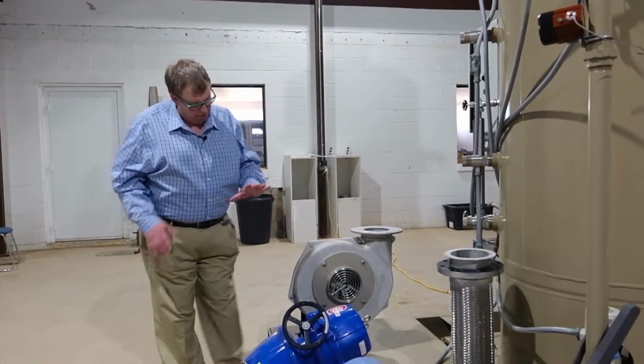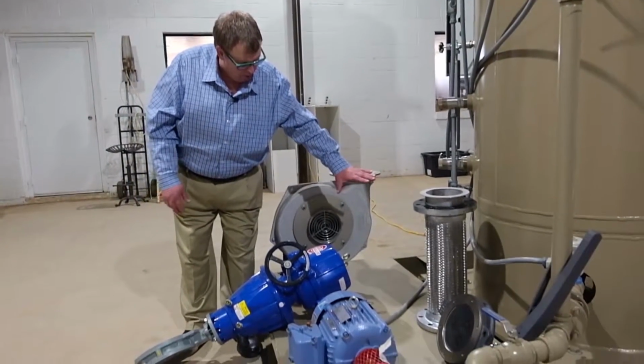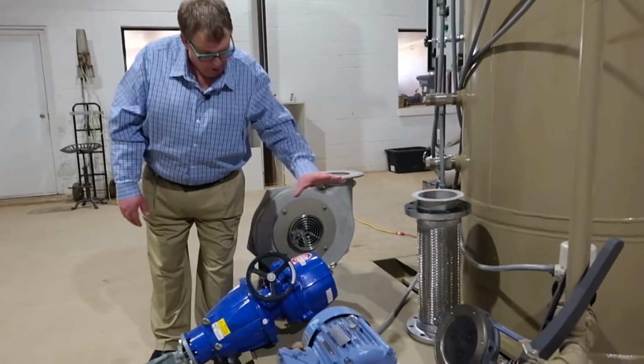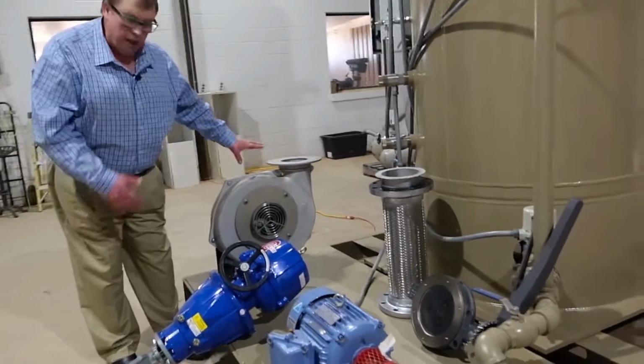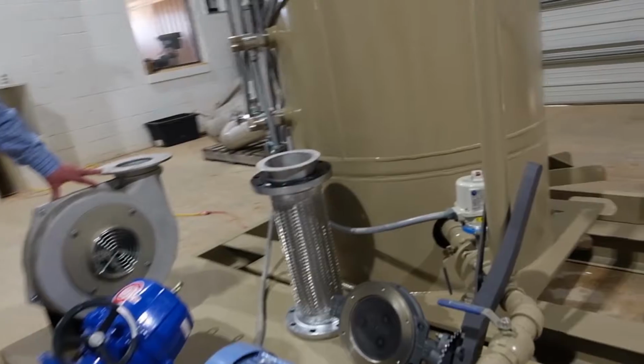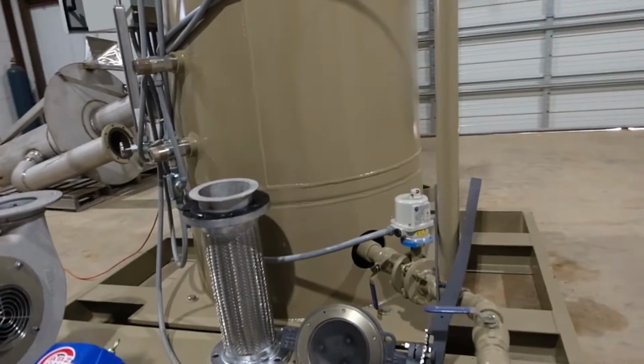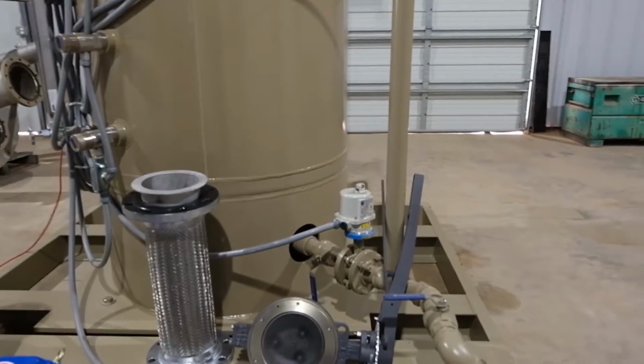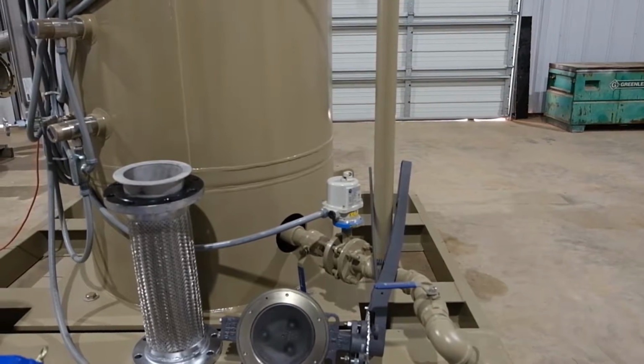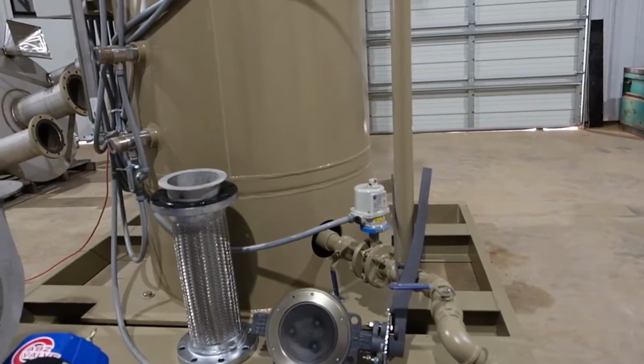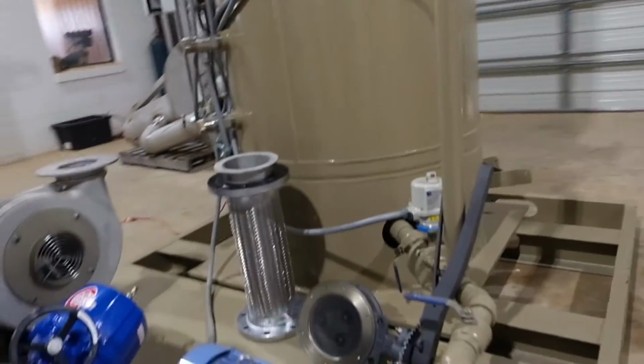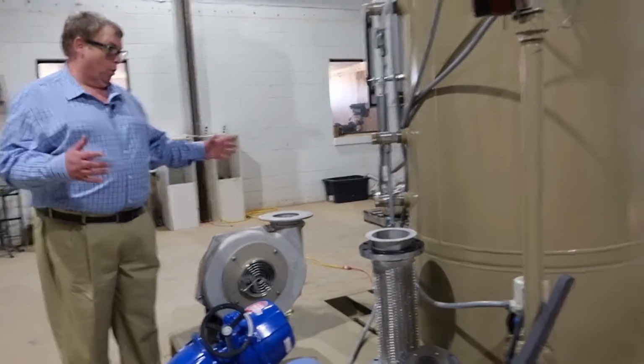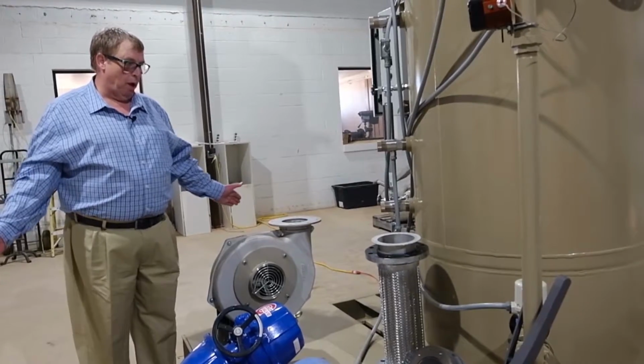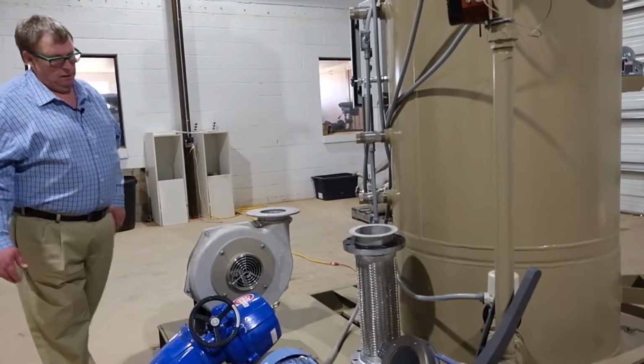Just downstream the safety valve, you've also got a stainless steel hose along with a manual valve. The hose is just to take out the vibration of the blower. The manual valve is there as a secondary safety feature in case you've got a situation where your flare is down or your blower is down. Not only do you want to use your safety valve, but you also want to manually close off that blower riser just to prevent any kind of possibility for an accident.